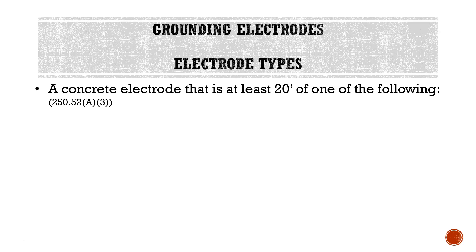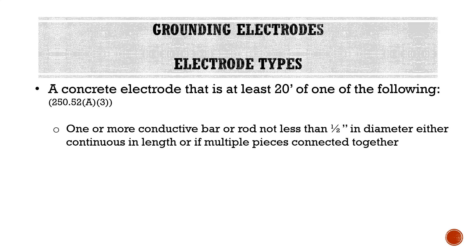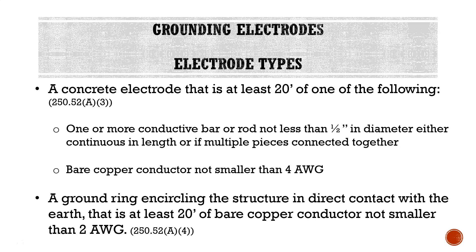A3, a concrete encased electrode that is at least 20 feet of one of the following: one or more conductive bar or rod, not less than a half inch diameter, either continuous in length or multiple pieces connected together; or bare copper conductor, not smaller than 4 AWG. A4 is a ground ring encircling the structure in direct contact with the Earth that is at least 20 feet of bare copper conductor, not smaller than 2 AWG. Keep in mind, these wire sizes are minimums — we can be required to use a larger wire size, but we do have a minimum.